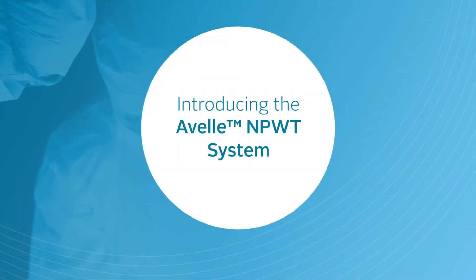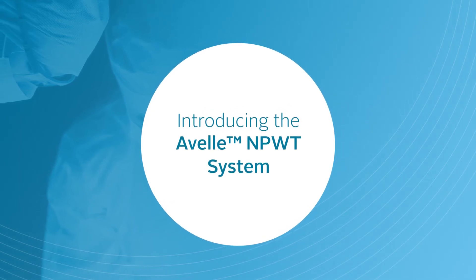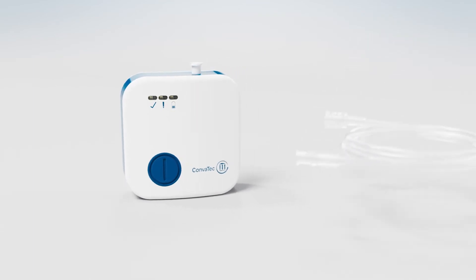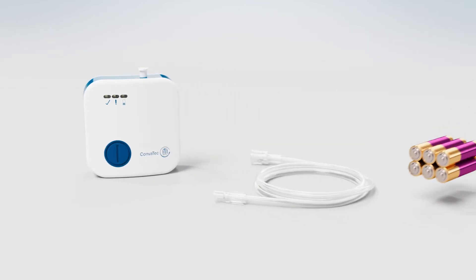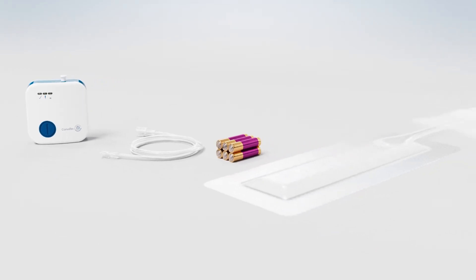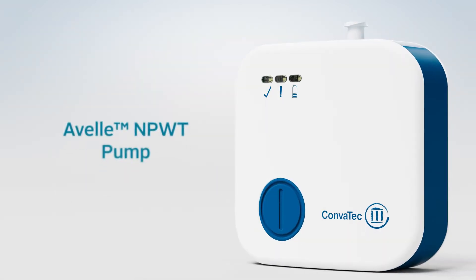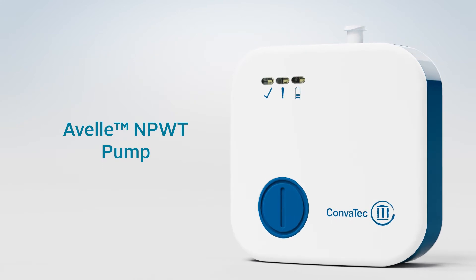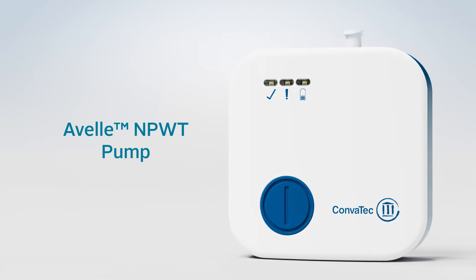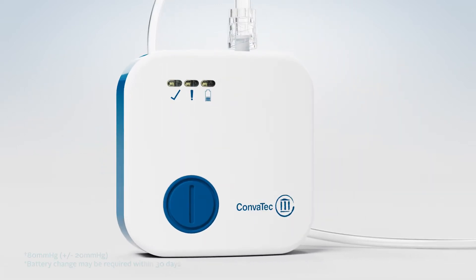The Avelle Negative Pressure Wound Therapy System is designed to manage surgical incisions and a broad range of other wound indications. The Avelle system consists of a non-sterile, single-use pump, supplied with tubing and two sets of lithium AAA batteries. Avelle dressing packs include a Hydrofibre Technology Negative Pressure Wound Dressing and six fixation strips. The Avelle pump is small, portable, and powered by lithium batteries, which enables up to 30 days of therapy and delivers 80 mmHg of negative pressure therapy to the wound bed.